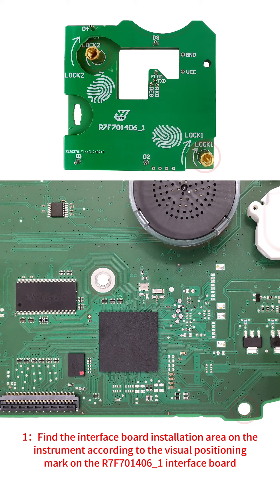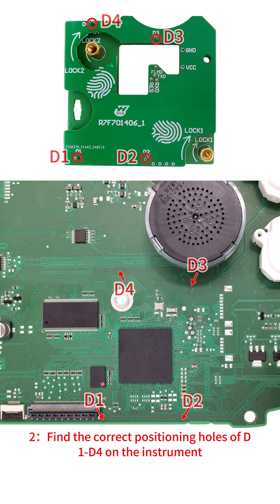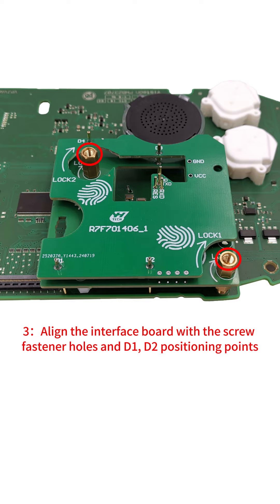Step 1: Find the interface board installation area on the instrument according to the visual positioning mark on the R7F701406_1 interface board. Step 2: Find the correct positioning holes of D1 to D4 on the instrument. Step 3: Align the interface board with the screw fastener holes and D1, D2 positioning points.